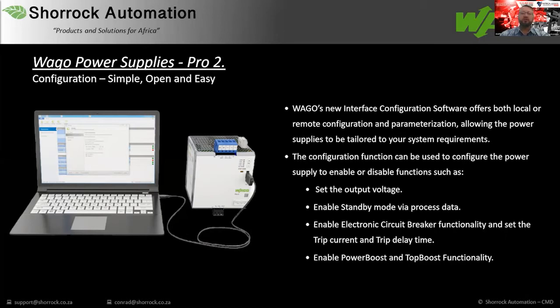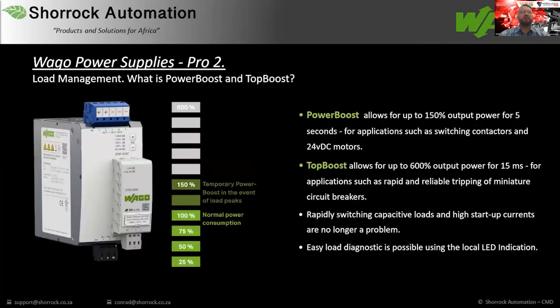In addition, WAGO also offers power boost and top boost functionality on our power supplies. Let me explain what power boost and top boost is. Power boost allows for up to 150% of the output power for 5 seconds for applications such as switching a contactor or 24 volt DC motors. This is typically when we need to compensate for the inrush current. In addition, we also offer top boost. Top boost allows for 600% output power for 15 milliseconds for applications such as reliable tripping of miniature circuit breakers. Rapid switching capacitive loads and high startup currents are no longer a problem.